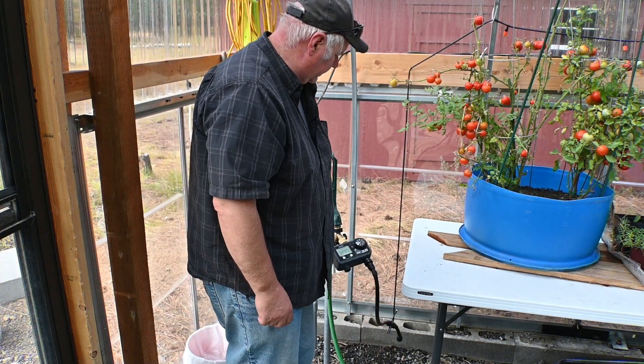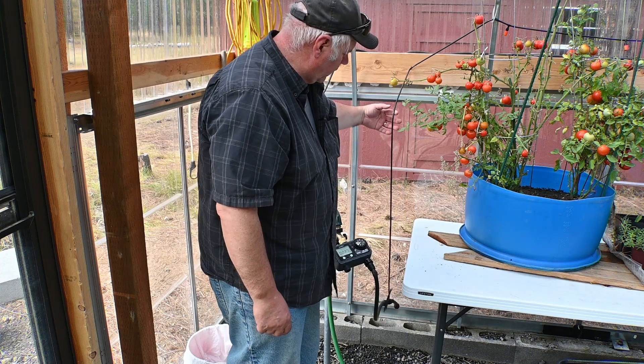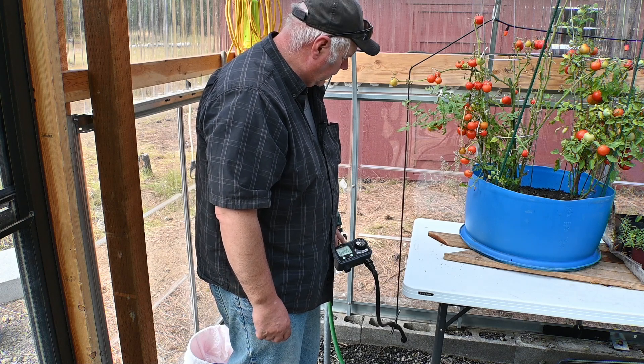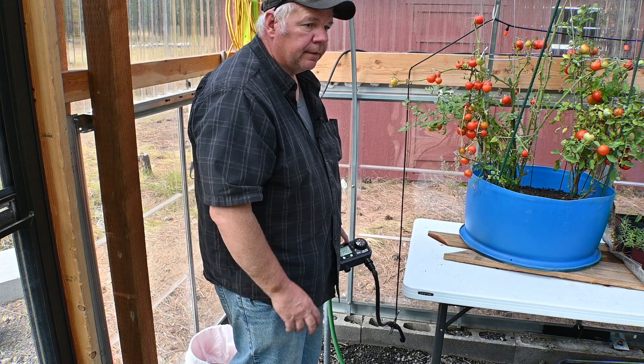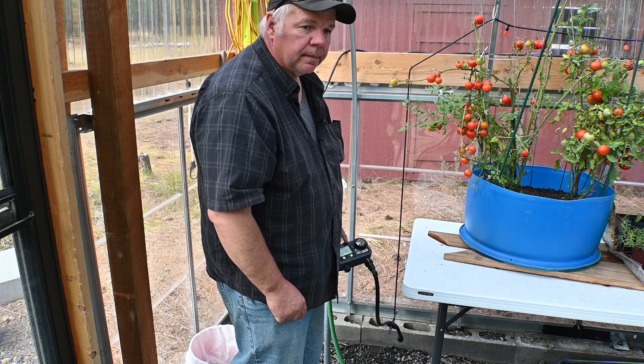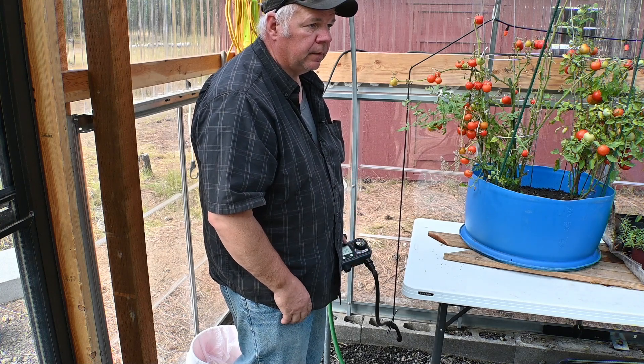You can still probably see me in the frame - there's a frost-free nozzle connected through a controller to an irrigation spray nozzle. The irrigation runs three times a day for five minutes each. If there's a target for humidity inside the greenhouse that we can't achieve, my wife changes it through this controller from three times to four times or five times - whatever the case may be - through that smart device I mentioned at the beginning of the video.